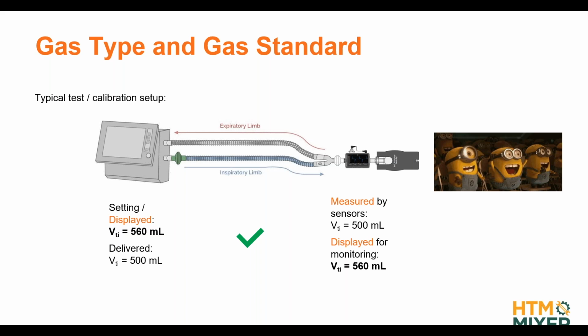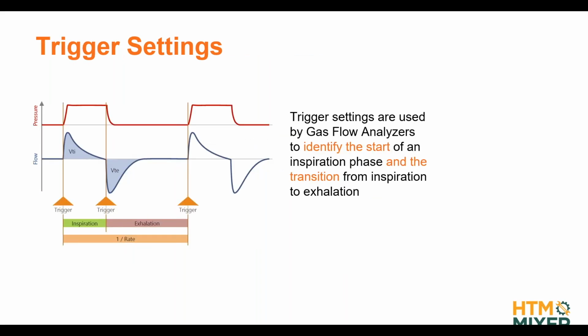All right, so again, the key takeaways: make sure that your gas type is set up correctly. So if you measure air, make sure that it's not set to CO2 or something like that. And even more important, the gas standard needs to match the device under test. Okay, let's go on with the next settings.